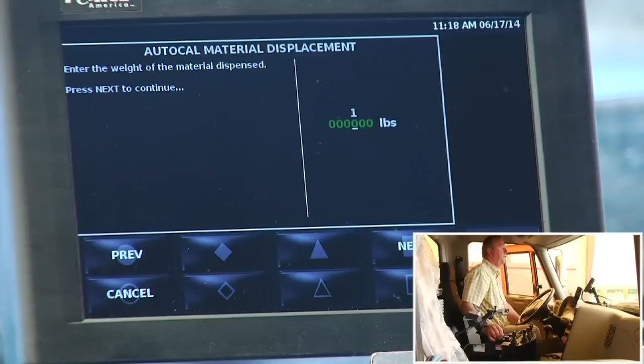So I'm going to press next, and I'm going to enter that 165 in here. So there's 165, and if I press next again, it's going to calculate the turns by the pounds for me. It says AutoCal has determined a value of 8.5 pounds per revolution. Press finish if you would like to use this value. So I'm going to press finish, and now it has entered 8.5 pounds into the material.